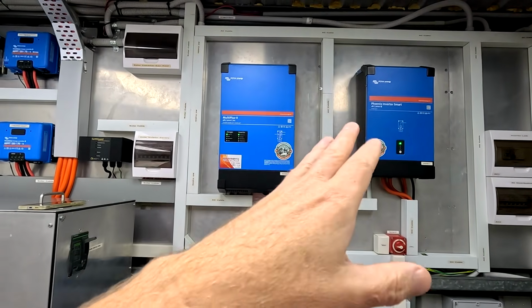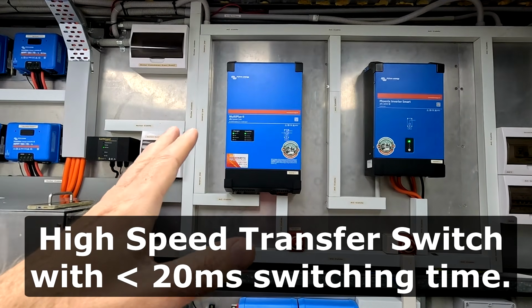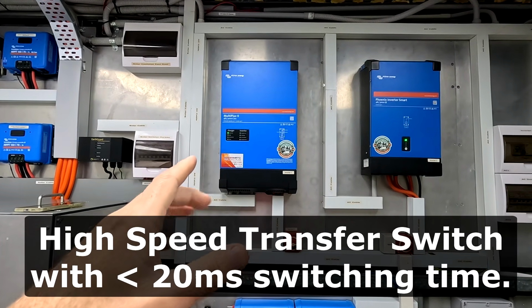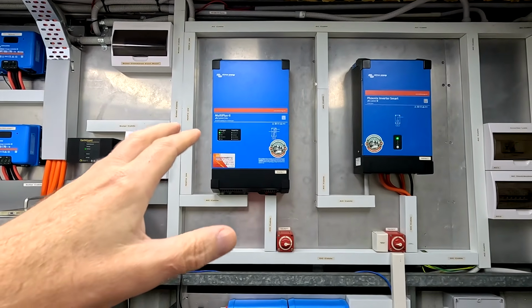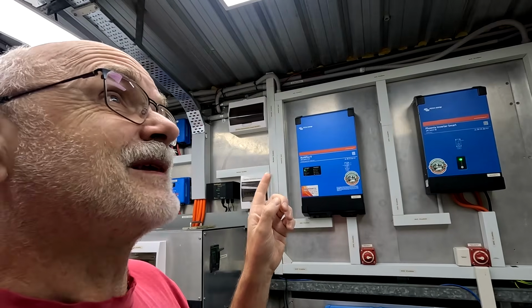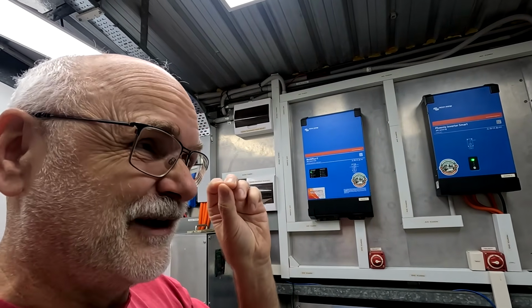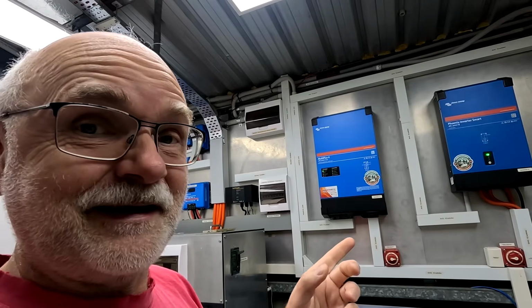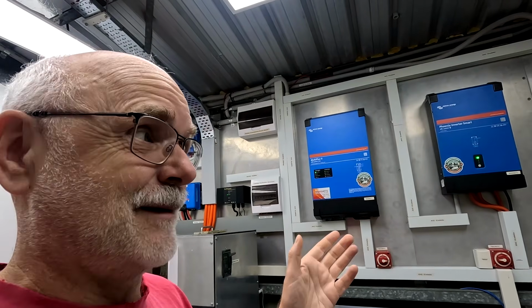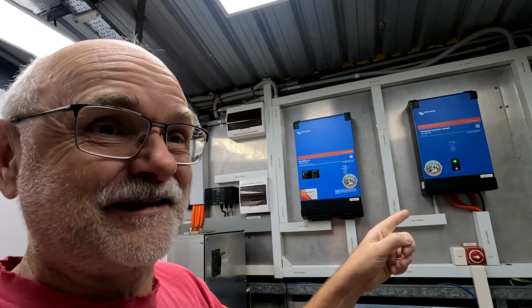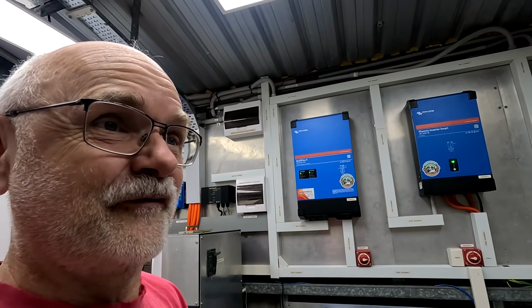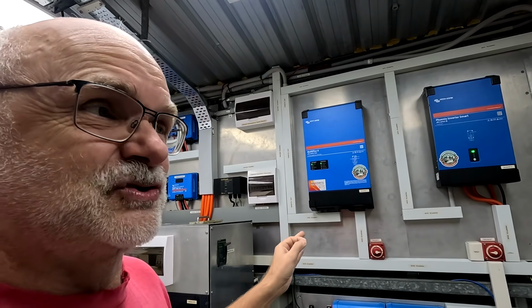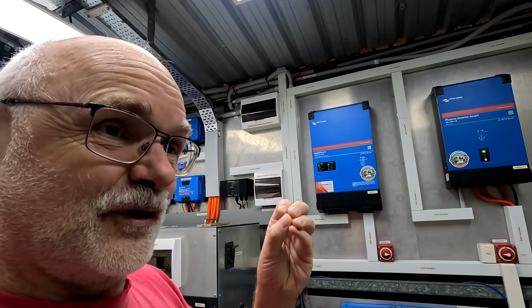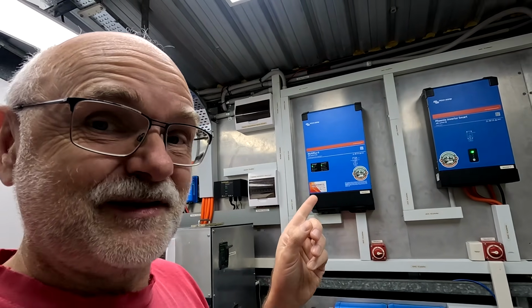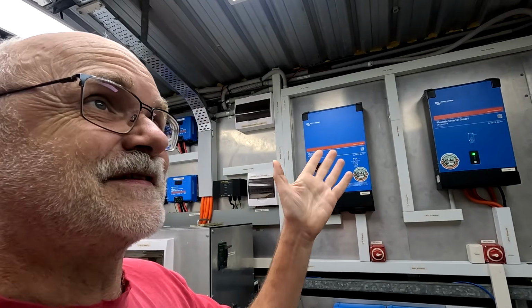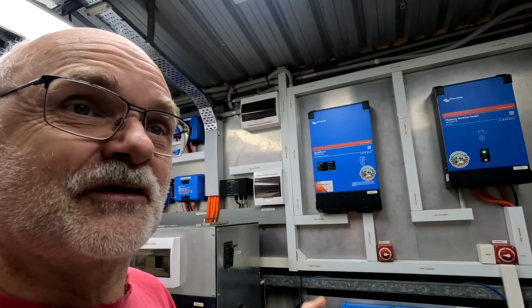And when the multi-plus turns off the Phoenix inverter again, I think it takes about 0.2 seconds or so until the multi-plus takes over the whole load again. And sometimes, depending on the light, you can see the light flickering for just a split second. So, last night, because of the higher load, we had this a couple of times that the Phoenix inverter kicked in, turned off, kicked in, turned off. And I could see the garden light outside, which is LED, flickering for just this 0.2 second when the multi-plus changes over again. But I couldn't see anything else inside the house.